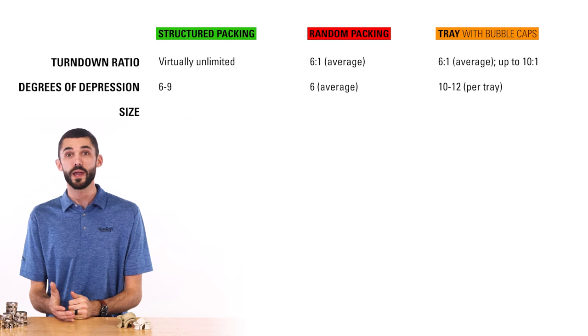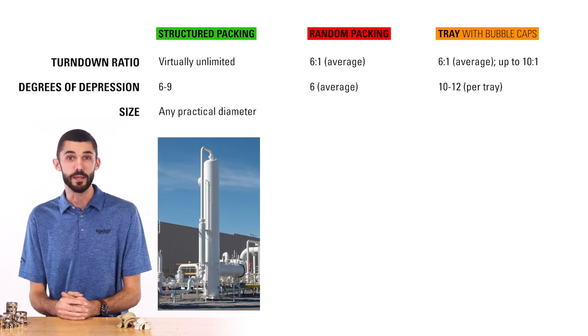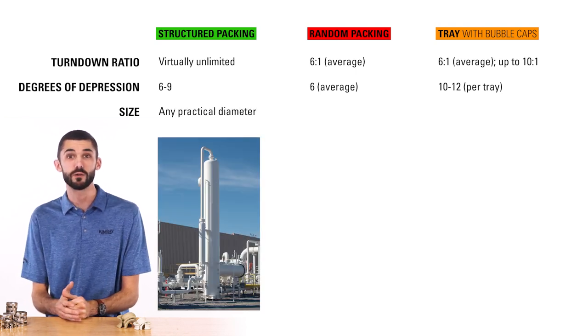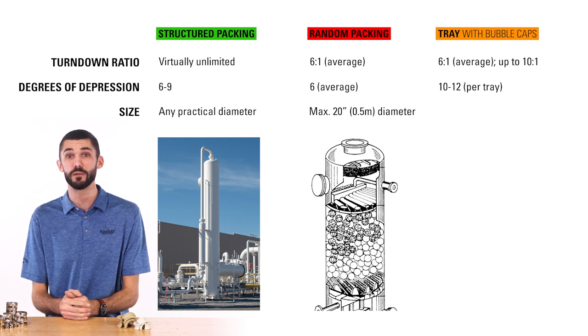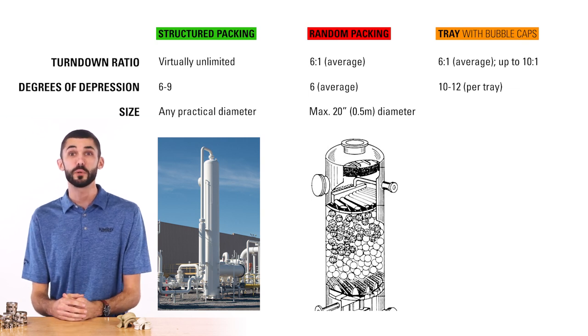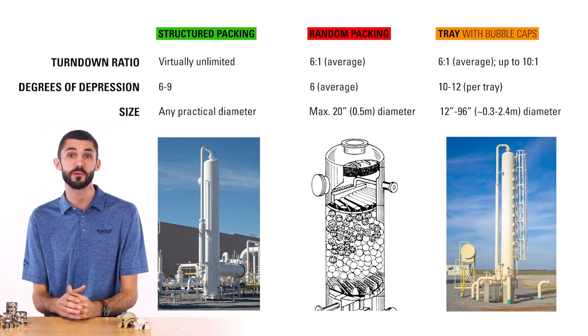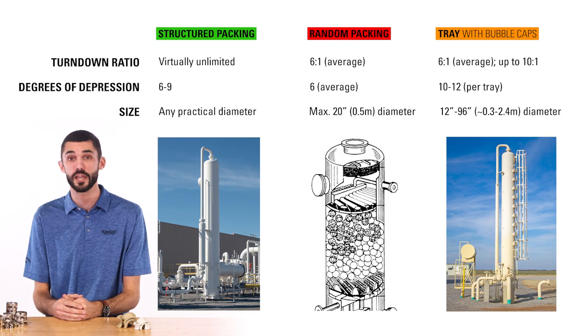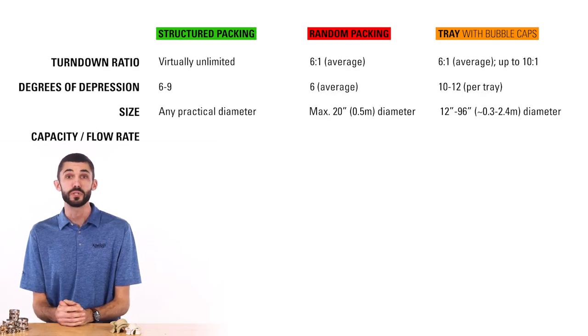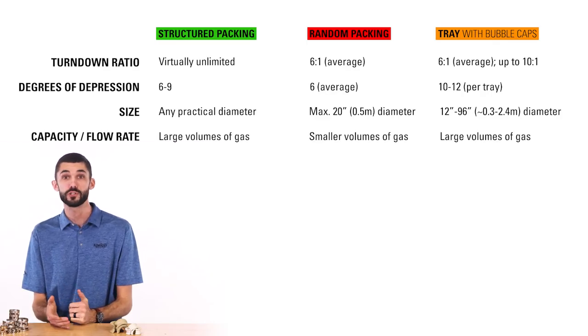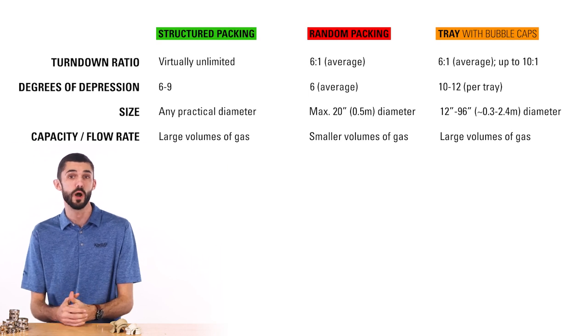A structured packed tower can be any practical diameter. Random packed towers have a maximum of 20 inch diameters — any larger diameter would inhibit the even distribution of glycol across the packing. A tray tower can range anywhere from 12 to 96 inches in diameter. Absorber capacity is primarily determined by the gas volume through the tower, so larger volumes of gas will need larger towers. Therefore, structured or tray designs are the two options for high-capacity applications.